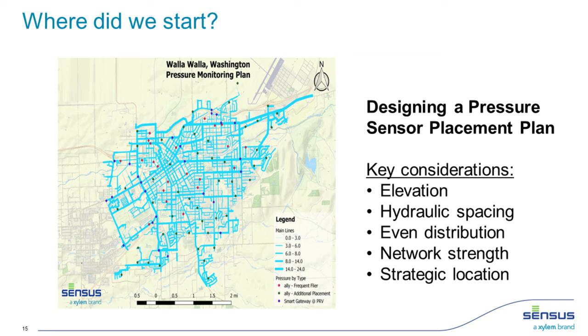We see people dithering those higher resolution sensors out there. Not just the smart gateway, but the Ally meter, you have to buy a radio that's unlocked to allow you to go below 1-hour MSRs. But you can dial the Ally down to, I think, 5 minutes. So you have some options there, but you're burning up more battery—talking 3-year or 4-year life versus a 20-year life. But you do have the ability to ratchet up that MSR.